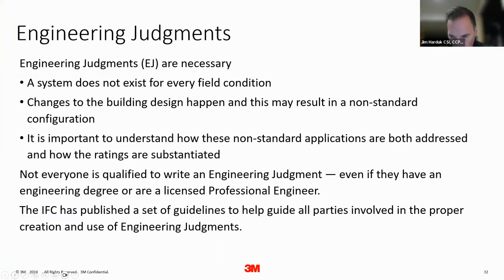So I can tell you that on just about every project I've ever been involved in, there will be a point in time in the job where we've gone through all of our listed systems and we can't find one particular drawing that addresses the field conditions. So basically, in situations where you have odd field conditions that nobody has tested to, and there's no listing or no tested system for, we have to issue what's called an engineering judgment.